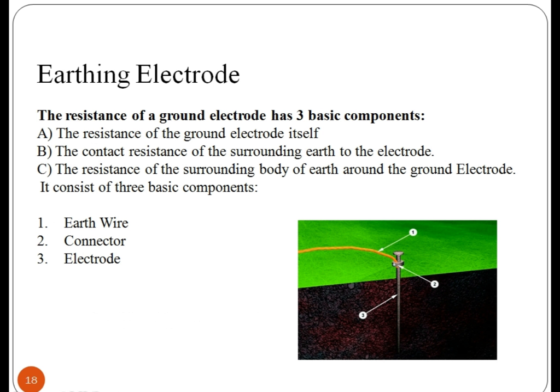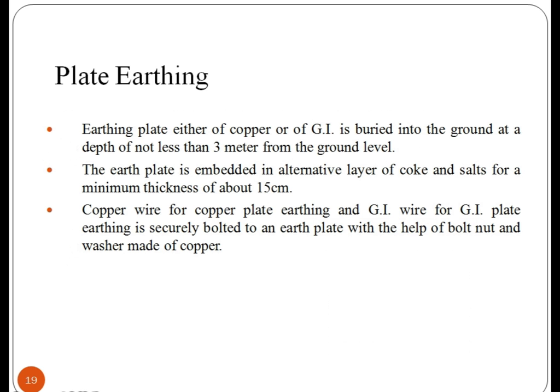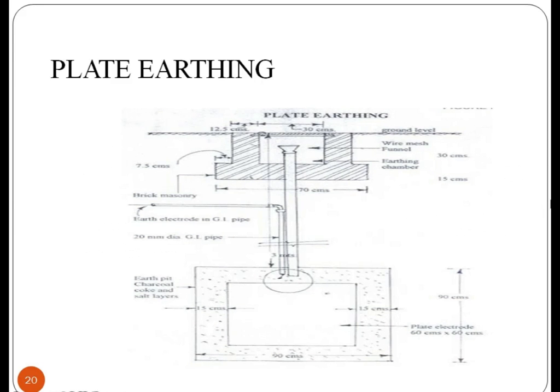Earthing electrode. The resistance of the ground includes the electrode itself and the connection to the electrode. It consists of three basic components: earth wire, connector, and electrode. Plate earthing. In this type of earthing, a plate of copper is buried in the ground at a depth of not less than 3 meters from the ground level. The earth wire is securely bolted to the earth plate with the help of a bolt, nut, and washer made of copper. You can see the plate earthing diagram where the earth plate is embedded in alternate layers of coke and salt for a minimum thickness of about 15 cm.